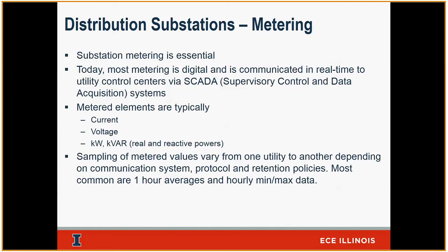Typically, we talk to these points and bring the data back once every minute. But I don't store it once every minute, that's a ton of data. So we average them, and what I end up storing is data based on 1 hour intervals. Every utility is different, but I'd say 90% of utilities store 1 hour data. Retention is also different. I retain 1 hour data for 10 years at Ameren, for example. If I have sub-hourly data, say 15 minutes, I might store that for a year, maybe 2 years. So every data point is a little bit different, but what you can take for granted is I have 1 hour average data, typically retained for 10 years.